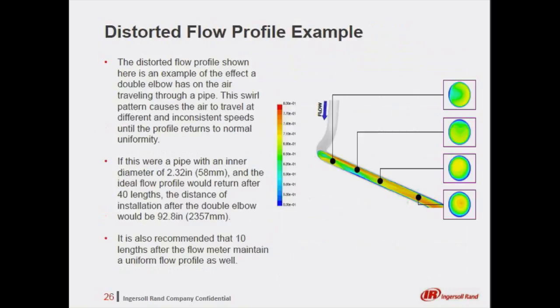The example seen here shows the reaction a pipe transition has on the compressed air's flow profile. This double elbow results in a swirl pattern which causes the air to travel at different speeds until it is able to return to normal uniformity.